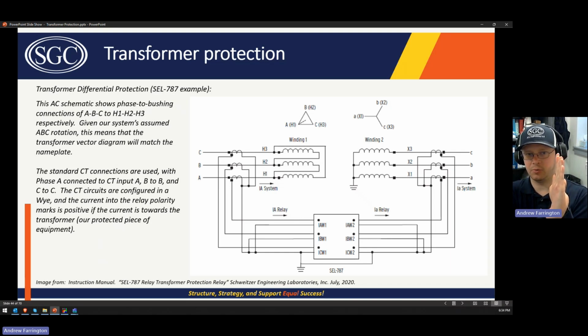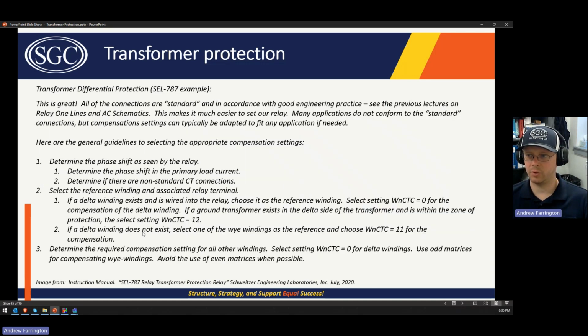Well, it doesn't want you to do that because there's an issue with the matrix math used for the differential calculations, and you can get a divide by 0 error that can cause the relay to misoperate. So I think most microprocessor based relays are similar because they all have this divide by 0 error. What they want you to do is actually set them both to 11. So the compensation is still the same, but they want you to use those odd numbered matrices whenever possible, because it avoids that divide by 0 error that you can get with even numbered matrices.